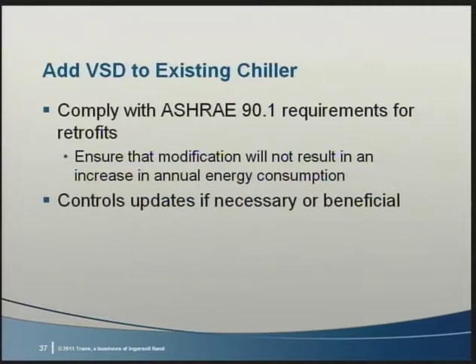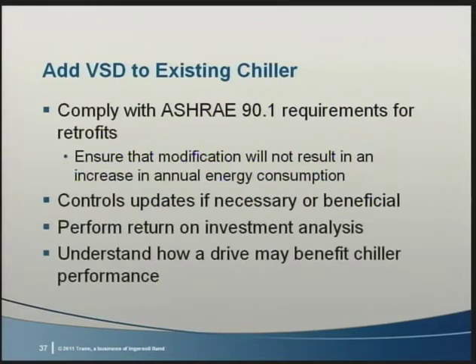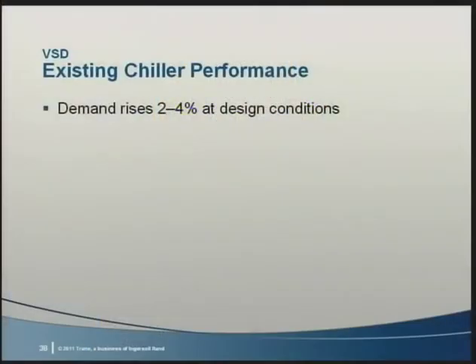And following that, you'll want to perform an economic analysis to determine if the payback meets your organization's criteria. When a drive is added to a chiller, there's an inefficiency added. If the chiller operates at design load, chilled, and condenser water temperatures, then this would result in a 2 to 4% increase in demand. So you would not normally put a drive on a chiller that operates at design conditions the majority of the time.